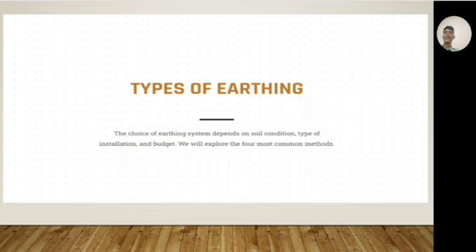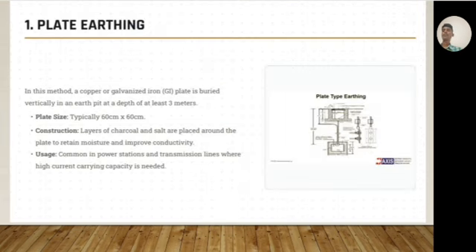Types of earthing. First point, plate earthing. In this method, a copper or galvanized iron plate is buried vertically in an earth pit at a depth of at least 3 meters. First point, plate size. Typically 60 centimeters by 60 centimeters.